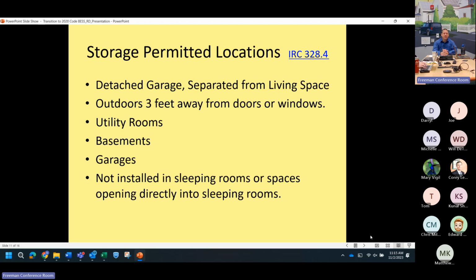Most of the newer lithium-ion batteries are designed to go mostly into living space, garages, or basements. But there are some that can be installed outdoors, and if you do so, you must be 3 feet away from doors or windows. Utility rooms and electrical rooms are permitted locations for batteries. Basements, that's where they all seem to go. Garages, that's an acceptable place. You may not install batteries into sleeping rooms or spaces directly opening into sleeping rooms.